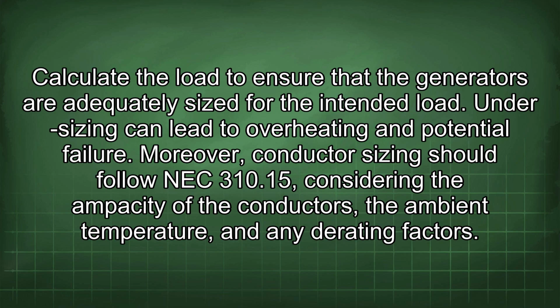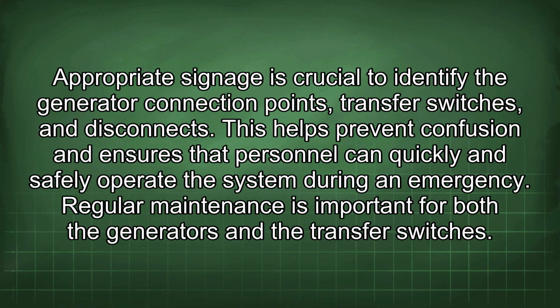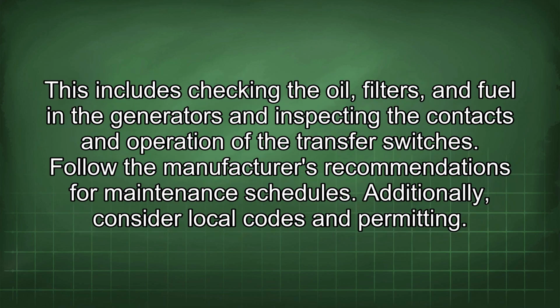Calculate the load to ensure that the generators are adequately sized for the intended load. Undersizing can lead to overheating and potential failure. Moreover, conductor sizing should follow NEC 310.15, considering the ampacity of the conductors, the ambient temperature, and any derating factors. Appropriate signage is crucial to identify the generator connection points, transfer switches, and disconnects. This helps prevent confusion and ensures that personnel can quickly and safely operate the system during an emergency. Regular maintenance is important for both the generators and the transfer switches. This includes checking the oil, filters, and fuel in the generators and inspecting the contacts and operation of the transfer switches.